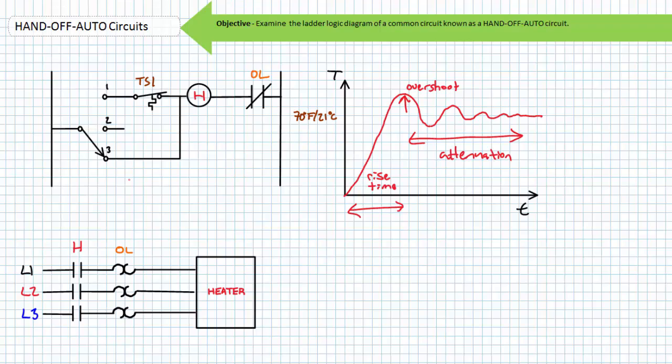The switch in position three is a manual bypass which energizes the H contactor coil and turns on the heater whether the temperature switch calls for it or not. The paint could be peeling off your walls and your goldfish could be belly up in a bowl full of boiling water and the heater would still be on at full blast in position three.